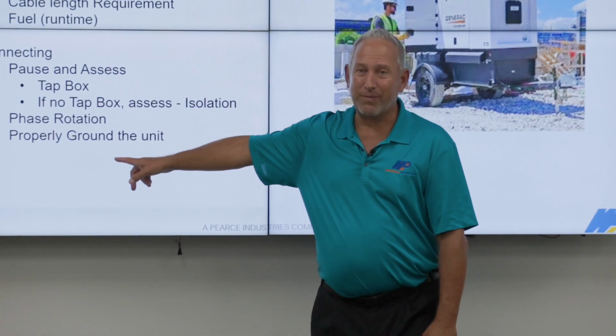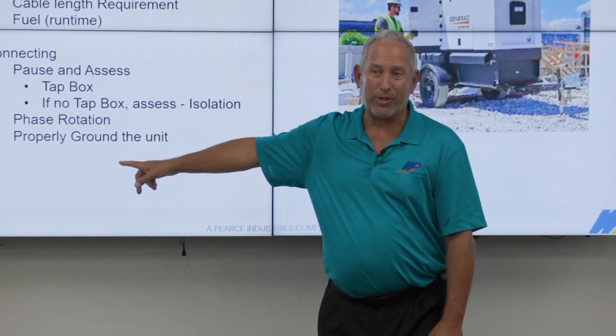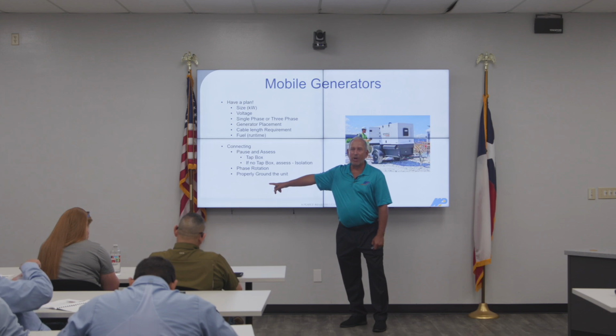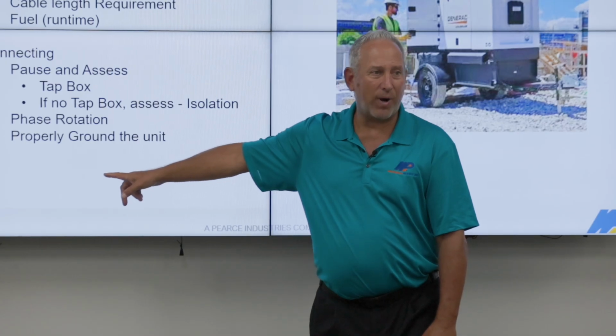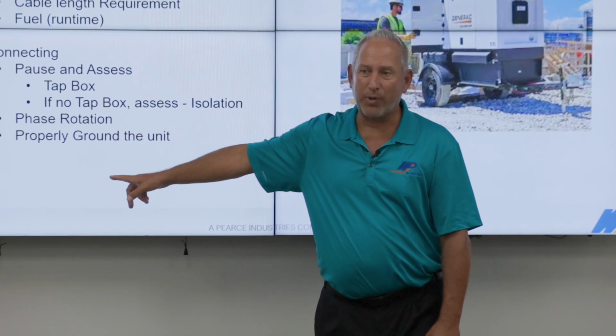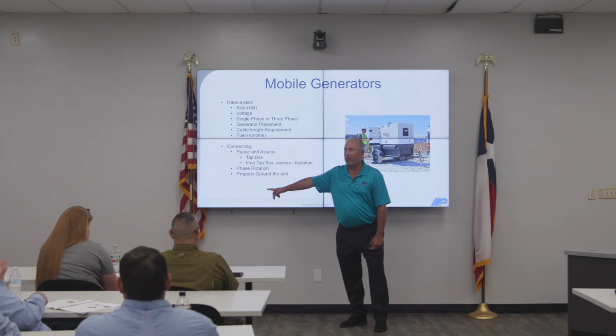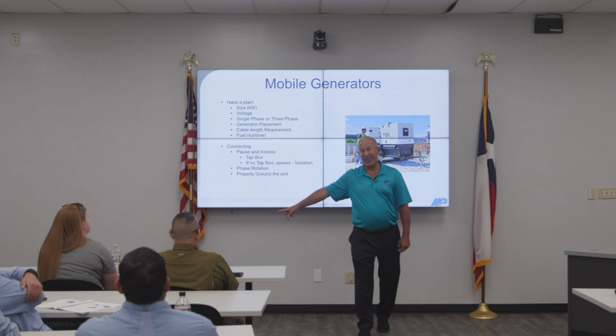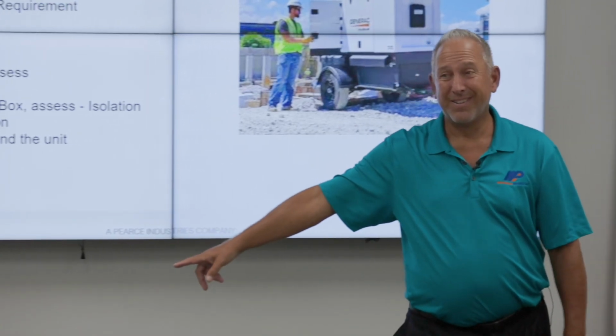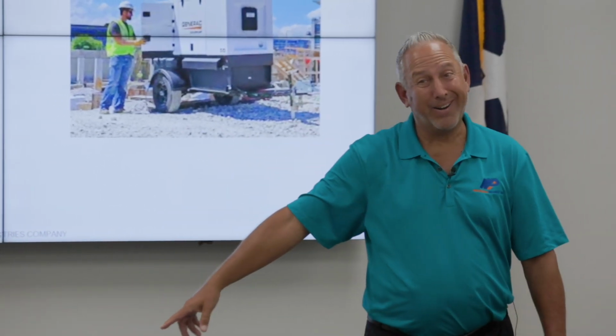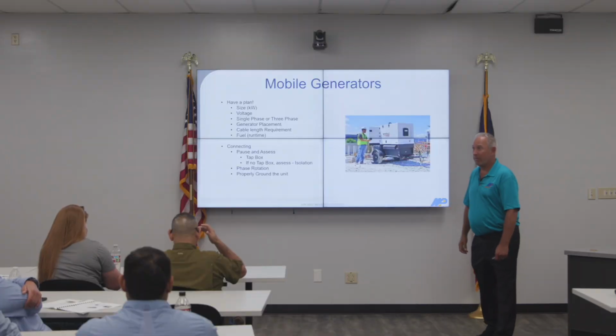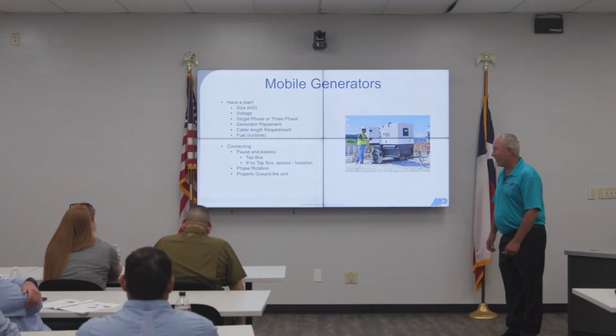For the love of God, ground the unit. Don't drive a rod in next to the gen - take your ground wire and run it to building ground. Ground the unit. Guess what? I bet the ground's going to be wet, so I'd want it grounded. Green first - ground first. Ground the unit, okay? Make sure you've got a good ground on that unit.